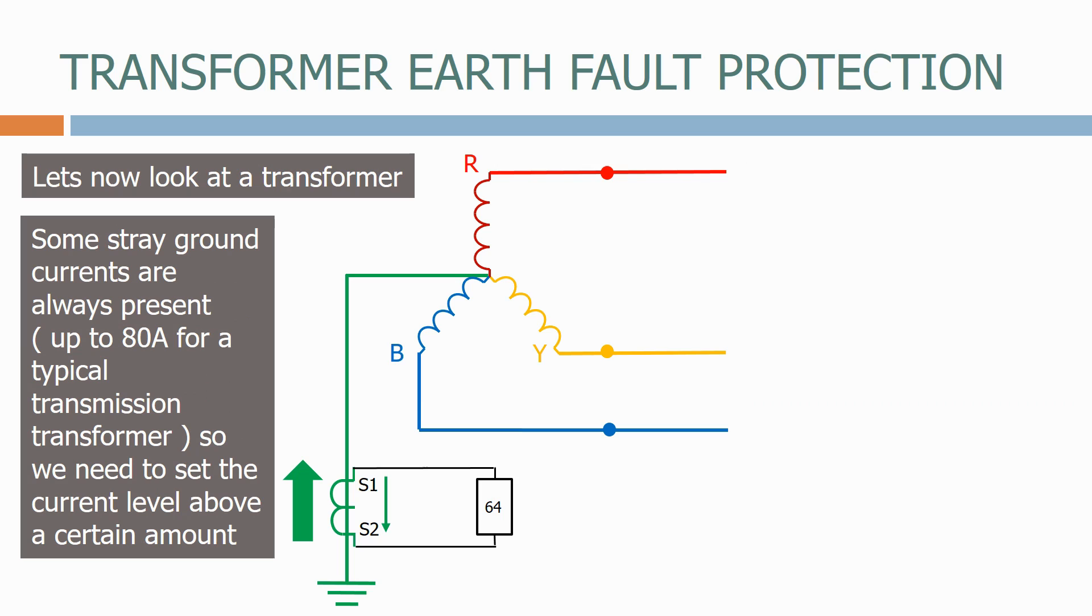Some stray ground currents are always present, up to 80 amps for a typical transmission transformer, so we need to set the current level above a certain amount.